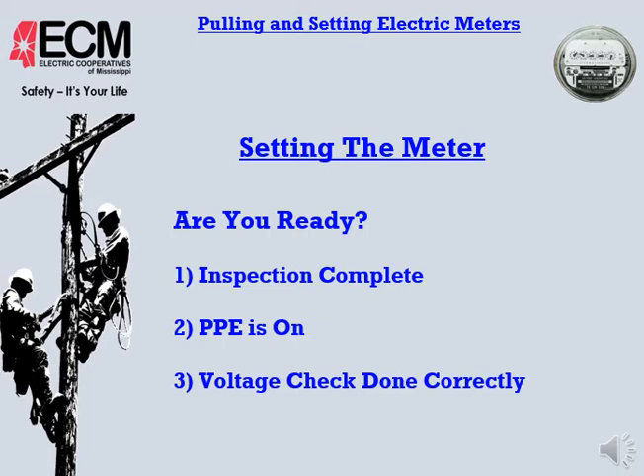Things to consider when we ask that question: one, is our inspection complete? Have we looked at this meter base from the transformer all the way to the meter base itself, and looked at it closely like we discussed? Have we found anything out of place that doesn't look right? Something that could cause a problem, maybe even set up a trap for us to get into. Keep in mind, the consumer isn't trying to set a trap for us, but they don't understand what they're fooling with, what they're playing with, and what hazards are involved.